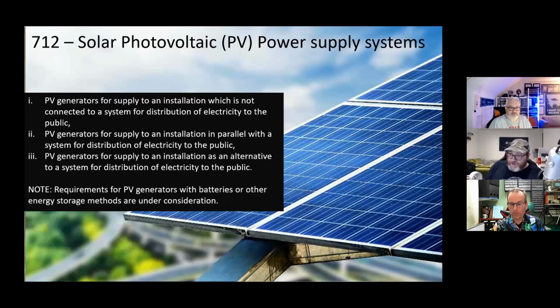The scope applies to either using PV generators to supply an installation which is not connected to a system for distribution of electricity to the public, so not feeding the grid, maybe like an island mode. Or PV generators supplying an installation in parallel, cross-connected with the grid as well. And generators for supply to an installation as an alternative, as a standby. So three different operation modes there, all within the scope.